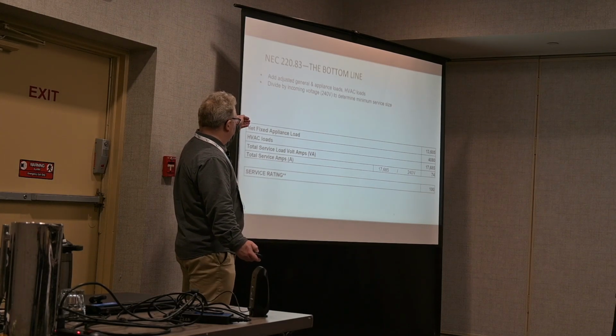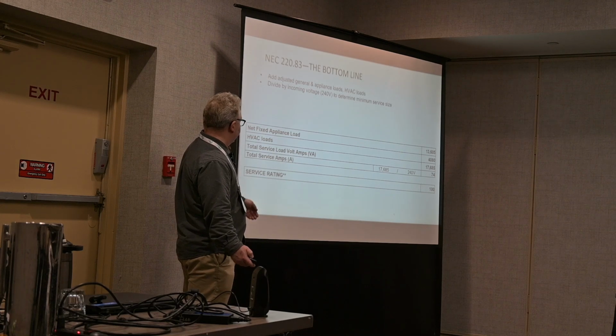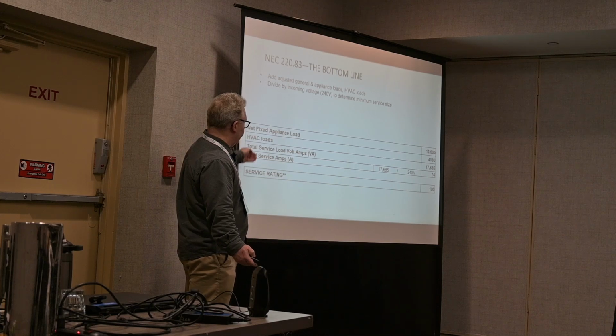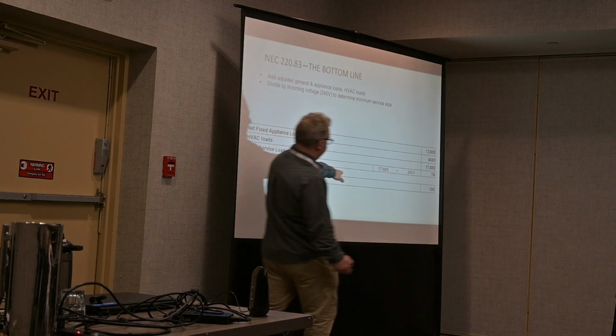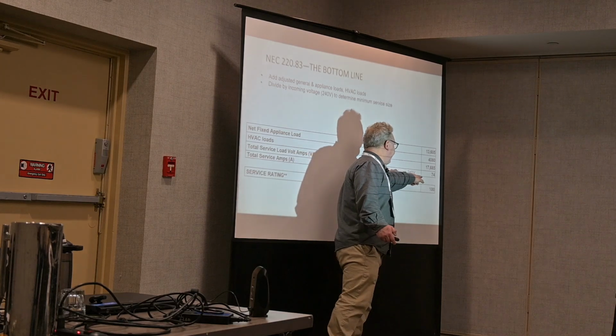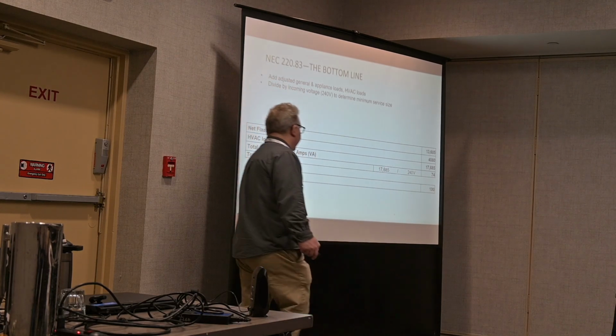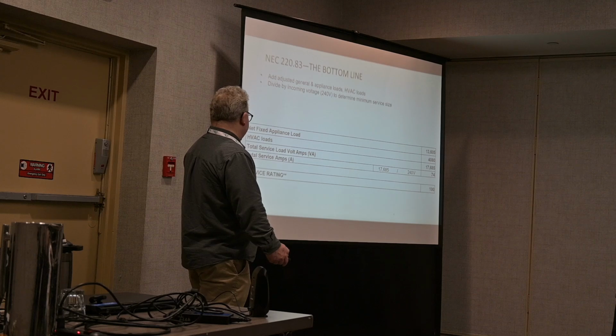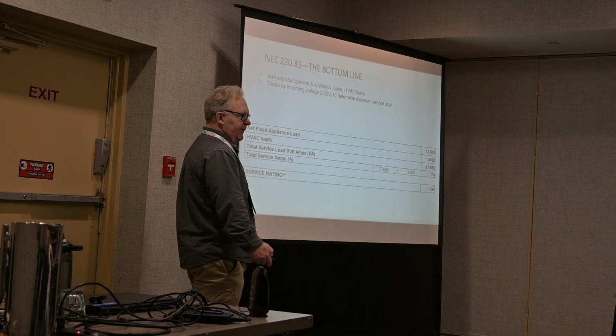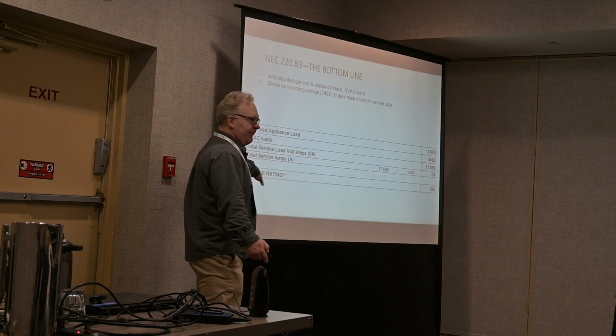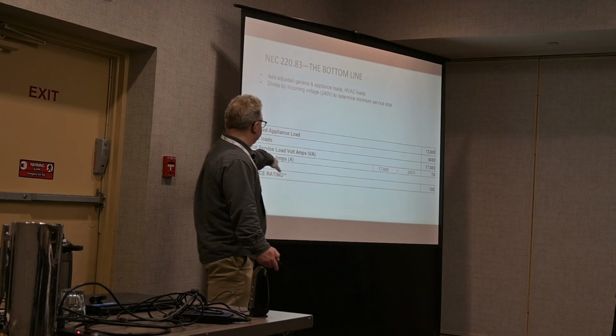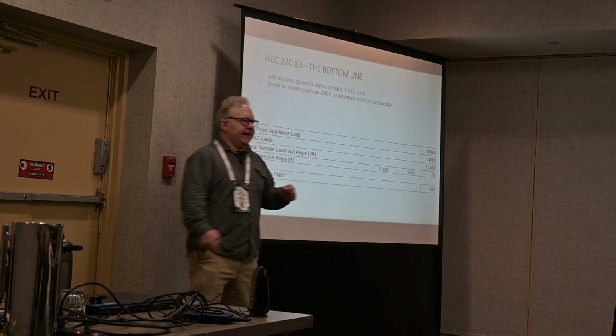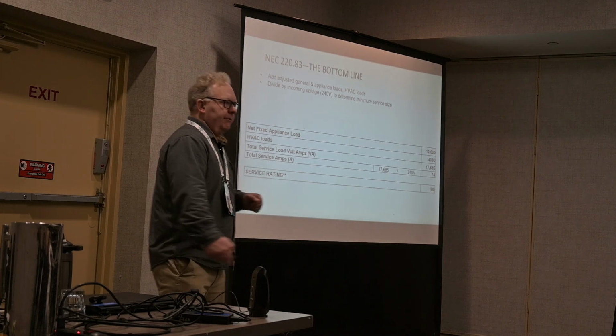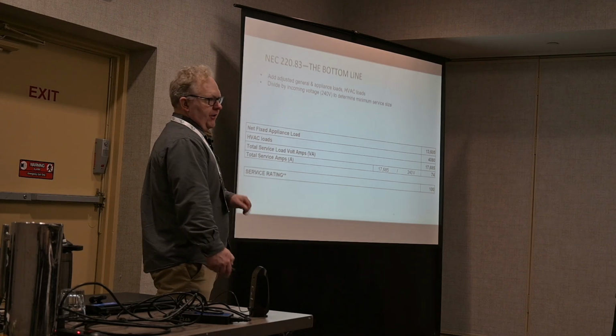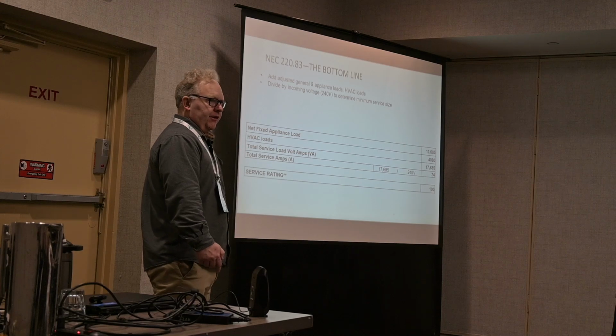And so we add our adjusted fixed appliance load and our HVAC load, and we get a total. We then divide that by our incoming voltage. And in this case, the number I'm getting here is 74 amps needed for this system. I have a 100 amp panel, so I'm good. And I actually have some room, if I wanted to add an electric vehicle charger, which is something I want to do in the future.